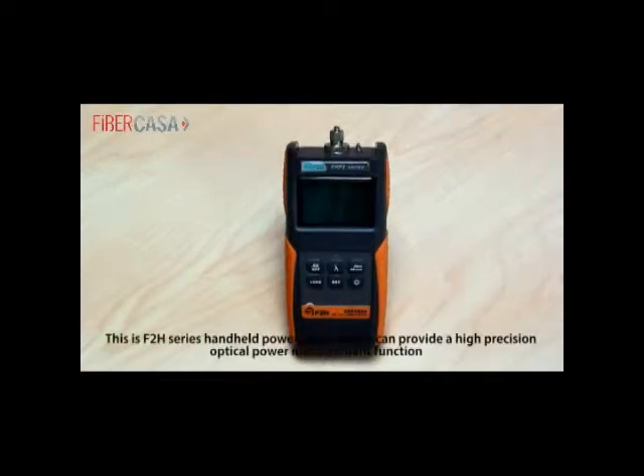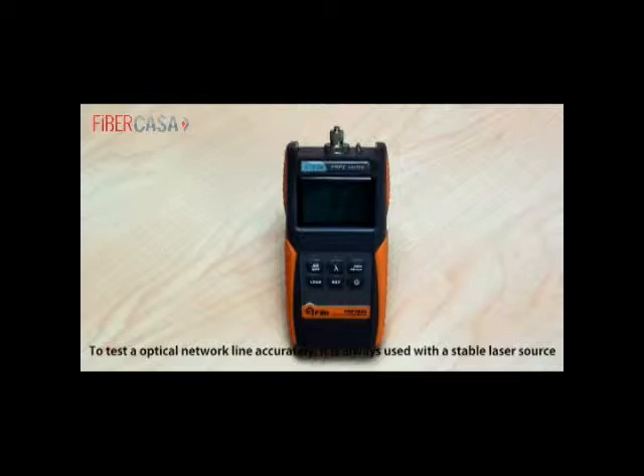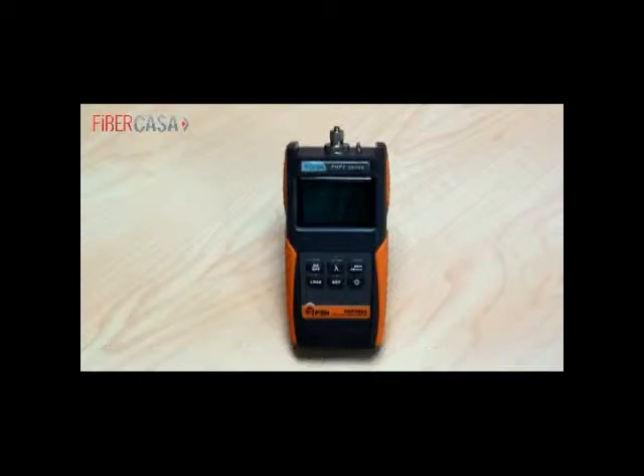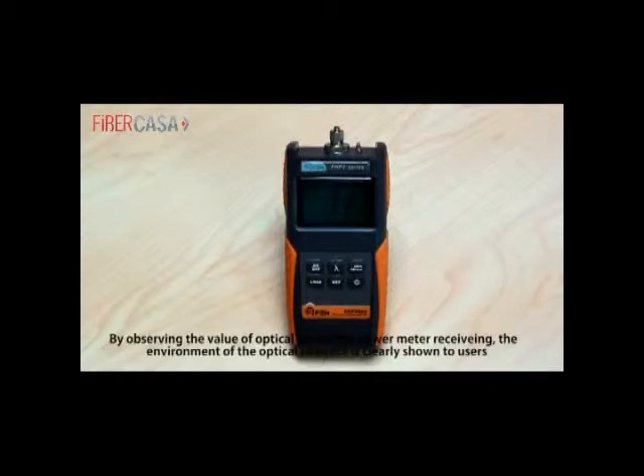This is F2H series handheld power meter, which can provide a high precision optical power measurement function. To test an optical network line accurately, it is always used with a stable laser source. By observing the value of optical power the power meter is receiving, the environment of the optical network is clearly shown to users.